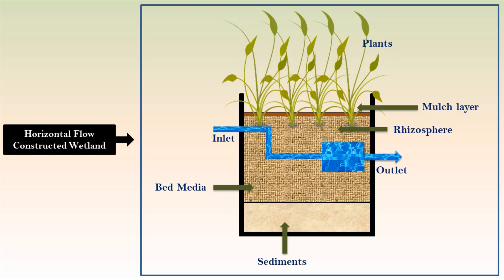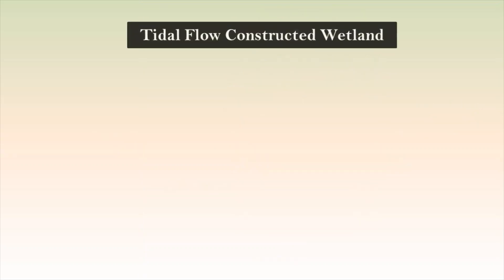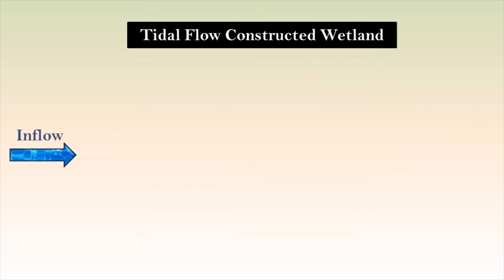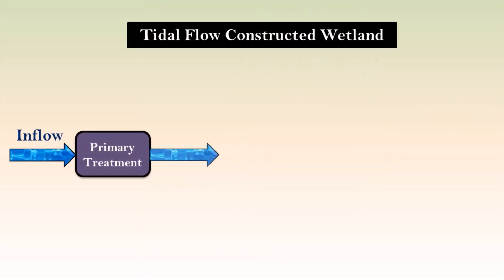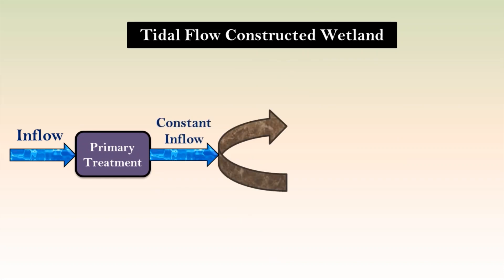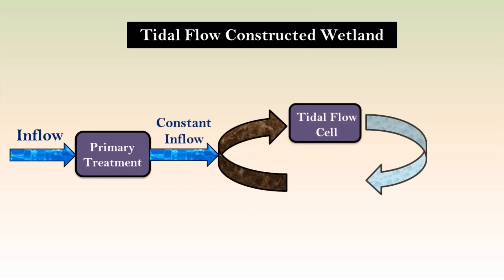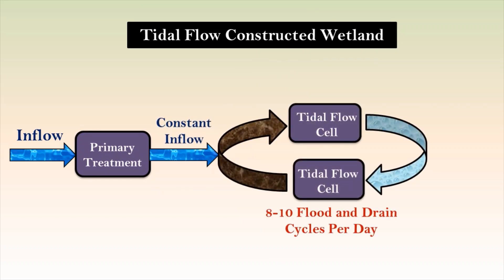Horizontal flow constructed wetlands require five to ten square meters per population equivalent when compared to vertical flow constructed wetlands, but they are efficient in denitrification. In order to increase aeration in the system, tidal flow constructed wetlands are effectively used, but they increase the energy footprint.